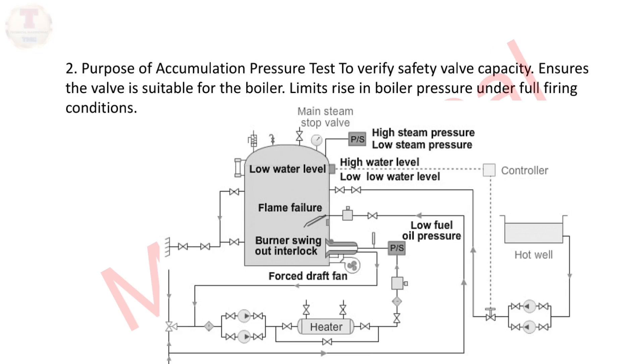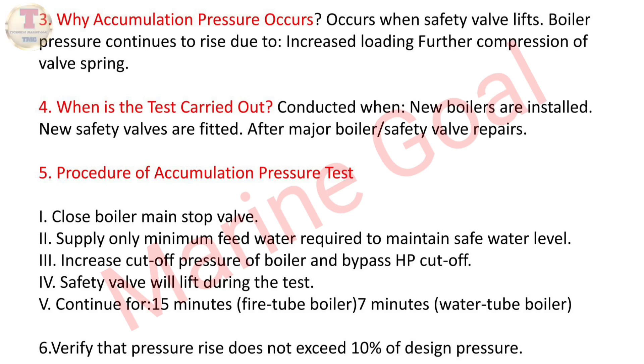Purpose of accumulation pressure test: to verify safety valve capacity and ensure the valve is suitable for the boiler, limiting rise in boiler pressure under full firing conditions. Accumulation pressure occurs when the safety valve lifts but boiler pressure continues to rise due to increased loading and further compression of the valve spring.